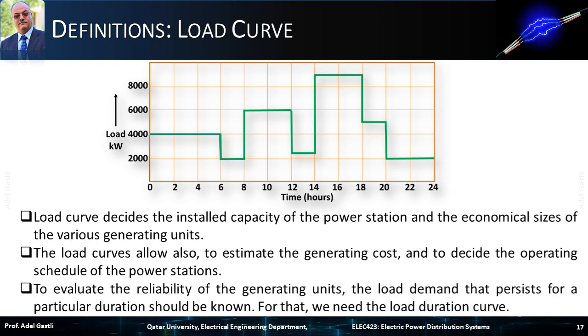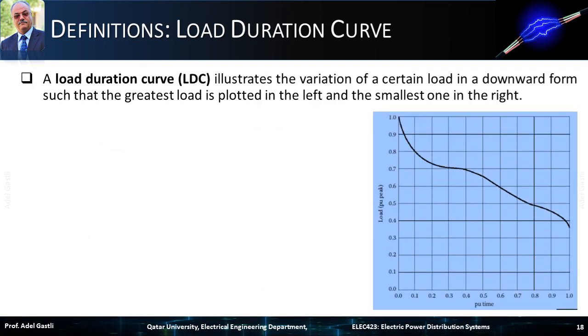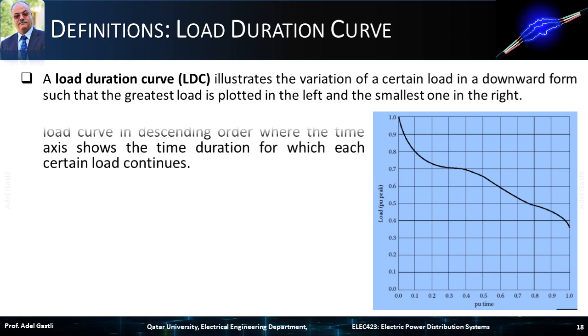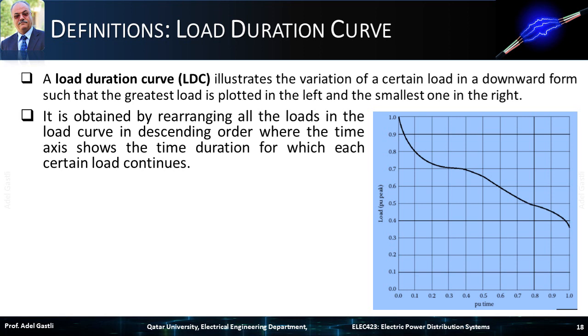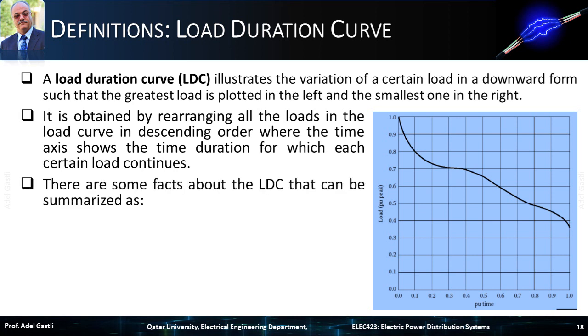To evaluate the reliability of the generating units, the load demand that persists for a particular duration should be known. A load duration curve illustrates the variation of a certain load in a downward form, such that the greatest load is plotted on the left and the smallest on the right. It is obtained by rearranging all the loads in the load curve in descending order, where the time axis shows the duration for which each certain load continues.